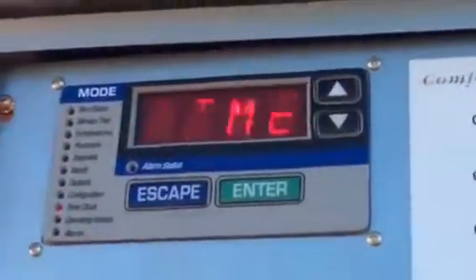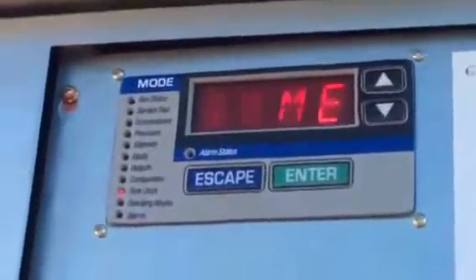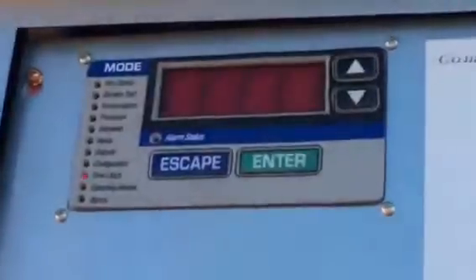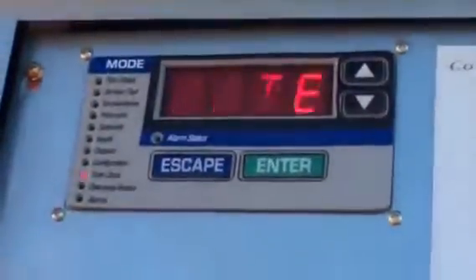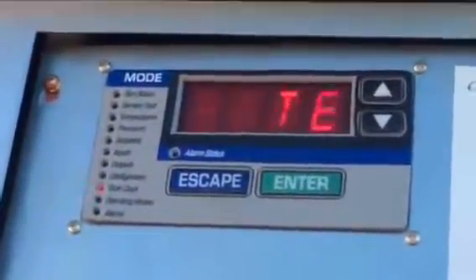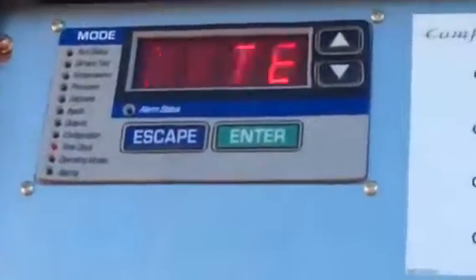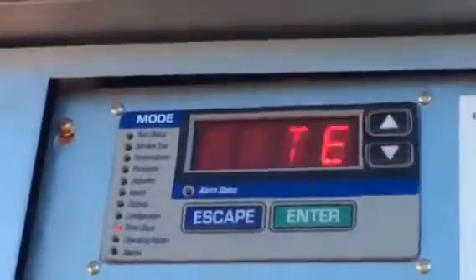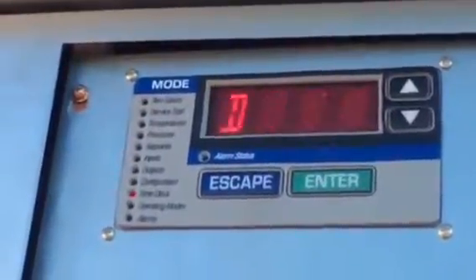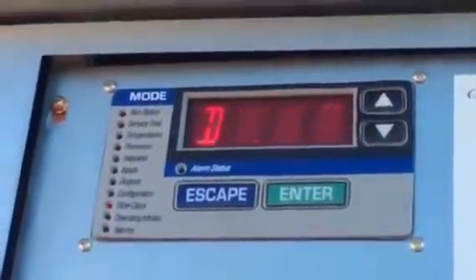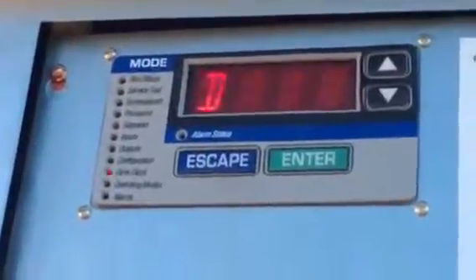I can look up set points, see things like the time clock is in here. It's also typically they're set up with a time and date, which is helpful for alarms. I can have time and a date. Month is January. So time and date set. If I get certain alarms or things that are happening, it's nice to know that it happens at startup every morning. Or I start getting an alarm that happens at 2 o'clock, 2:30 every day. Knowing that that's when it happens is very helpful to try to help figure out what's going on.